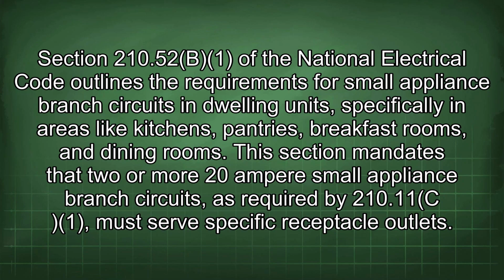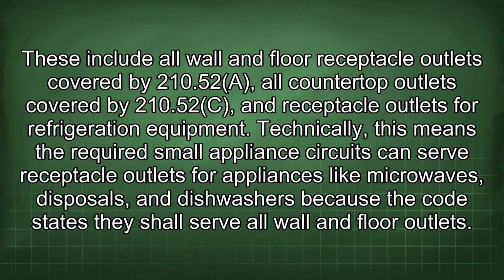Section 210.52 of the National Electrical Code outlines the requirements for small appliance branch circuits in dwelling units, specifically in areas like kitchens, pantries, breakfast rooms, and dining rooms. This section mandates that 2 or more 20-ampere small appliance branch circuits, as required by 210.11, must serve specific receptacle outlets. These include all wall and floor receptacle outlets covered by 210.52(A), all countertop outlets covered by 210.52(C), and receptacle outlets for refrigeration equipment.